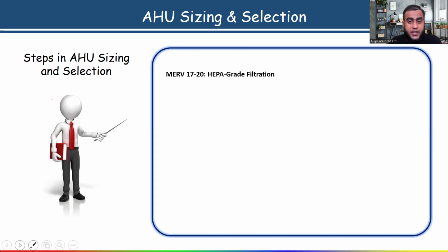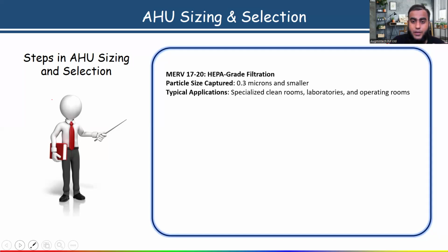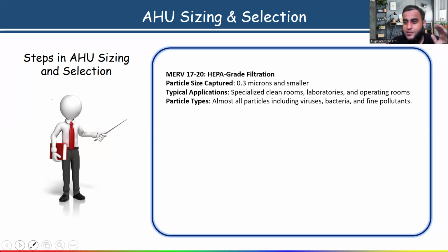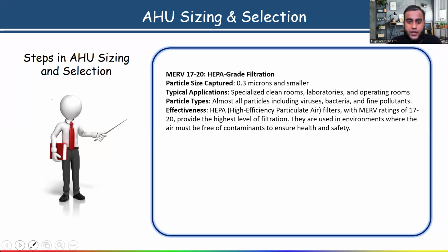MERV 17 to 20, HEPA grade filtration. It can capture 0.3 micron and smaller particles. Typically, its application is specialized clean rooms. Generally, we are using this HEPA grade filtration. Which type of particles can it capture? Almost all particles, including viruses, bacteria, and fine pollutants. It is a HEPA grade filter. HEPA stands for high efficiency particulate air filter, all of you know that. With MERV rating 17 to 20, it provides the highest level of filtration. They are used in environments where air must be free of contaminants to ensure health and safety.